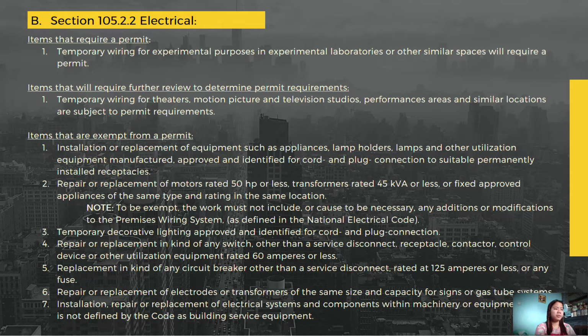Take note that to be exempt, the work must not include or cause to be necessary any additions or modifications to the premises wiring system as defined in the National Electrical Code. So, number 3, temporary decorative lighting approved and identified for cord and plug connection. Next, repair or replacement in kind of any switch other than a service disconnect, receptacle, contactor, control device, and other utilization equipment rated 60 amperes or less.